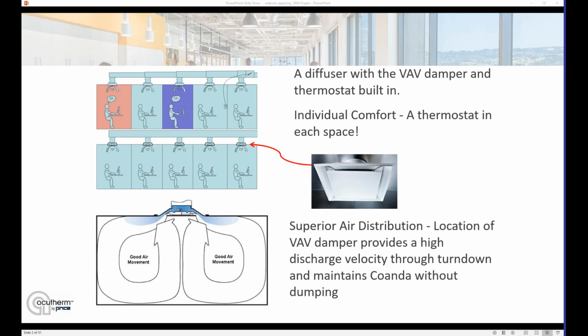By having a thermostat in each diffuser, you can create very small zones of control and provide very good comfort through individual selections of set points. Also, by having a VAV damper in each diffuser, it does produce a superior air distribution by constantly maintaining a very high discharge velocity even at low air volumes, and thus mixing the room quite well at all times.